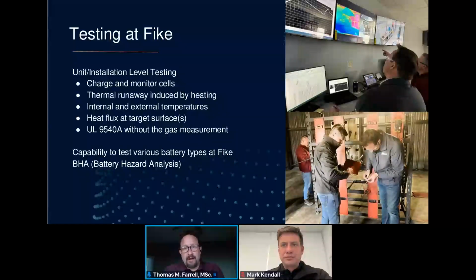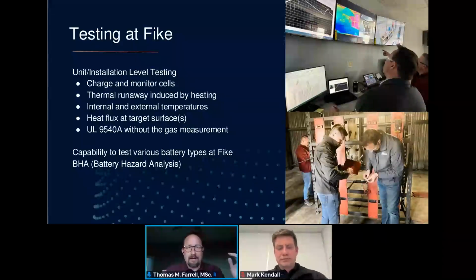You can do this with a nail puncture, but a nail puncture actually ends up releasing less energy than heating of the cell. That's partially because during a puncture, you start thermal runaway in a very small spot, whereas with heating, the entire pouch gets very close to the point of thermal runaway failure. Then when one spot eventually does go into thermal runaway, the whole battery goes immediately, releasing the maximum amount of energy. So we're always very conservative in our tests.